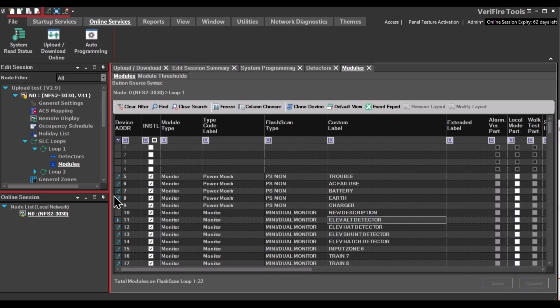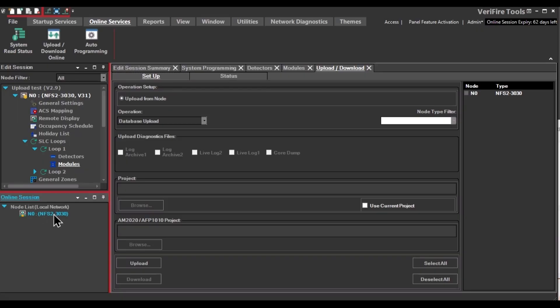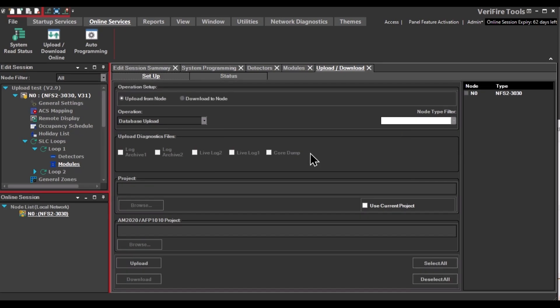Now, if you want to download those changes into the panel, you have to click Upload Download. When you look over here, you notice Upload's available but not Download because you're not logged into the panel. Double-click on the panel in the lower left. And then enter your installer passcode to log on to the panel. Now you have the option to download to the node by clicking here.